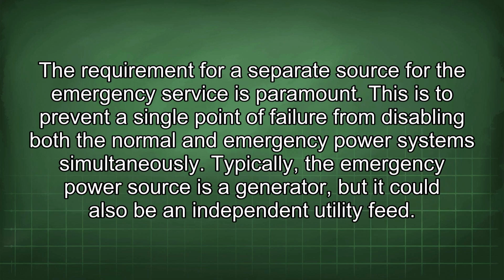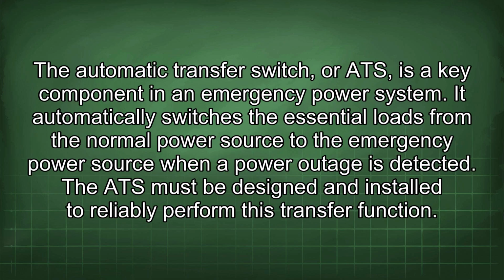The requirement for a separate source for the emergency service is paramount. This is to prevent a single point of failure from disabling both the normal and emergency power systems simultaneously. Typically, the emergency power source is a generator, but it could also be an independent utility feed. The automatic transfer switch, or ATS, is a key component in an emergency power system. It automatically switches the essential loads from the normal power source to the emergency power source when a power outage is detected. The ATS must be designed and installed to reliably perform this transfer function.